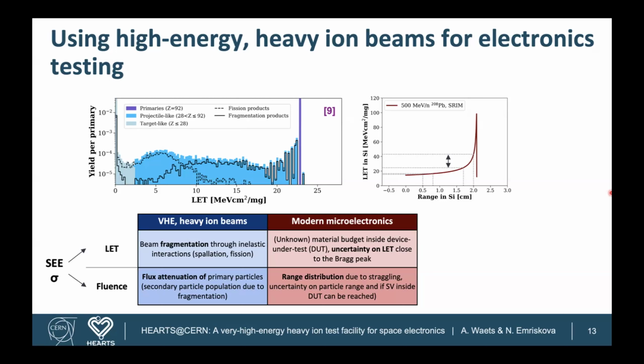There is not much variability in terms of LET. However, if you're already going to a depth of 1.5 centimeters or even beyond that, very close to a Bragg peak, so close where the particle is going to stop, there you have a variation of almost 20 LET points, so quite a lot. Because of the straggling of the energies of the particles, which is also happening in a rather probabilistic way, there's an uncertainty on the particle range within the device, and you're not even sure if the sensitive volumes can be reached.